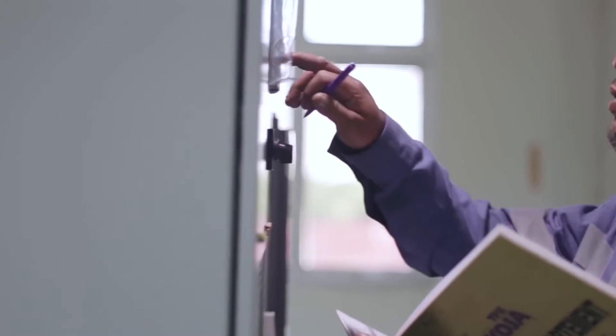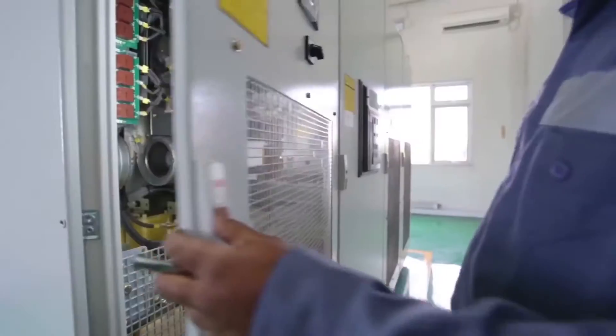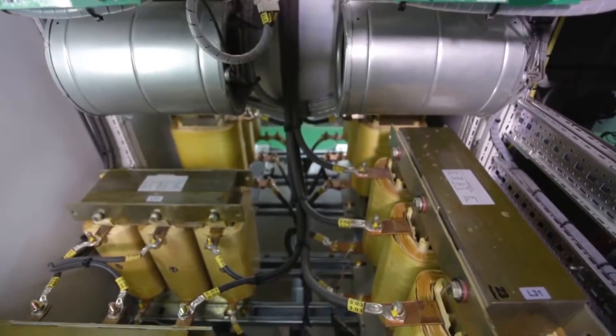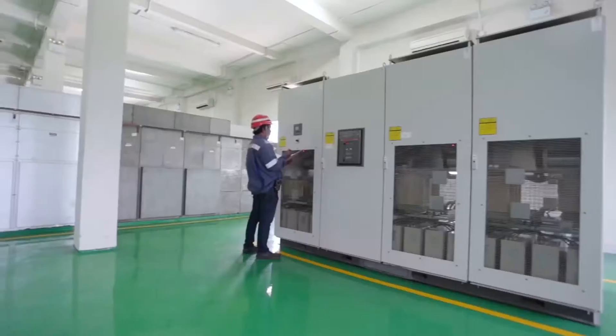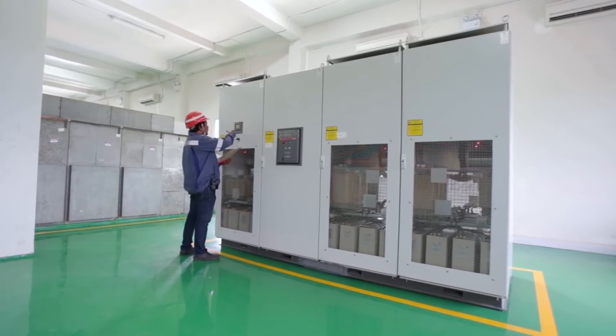Something had to be done. Hitachi Energy designed and supplied a thyristor-based compensation system called Dynacomp. Dynacomp is a low voltage capacitor bank which can be used for ultra-rapid power factor compensation caused by large loads such as cranes. It reduces demands on the electrical network by instantaneously compensating the reactive power. The response of Dynacomp is transient free, enabling voltage dip minimization and an improvement in power factor from 0.6 to 0.97, compliant with utility standards.